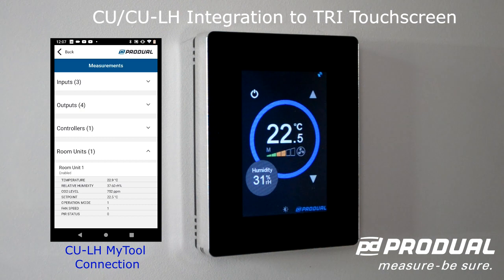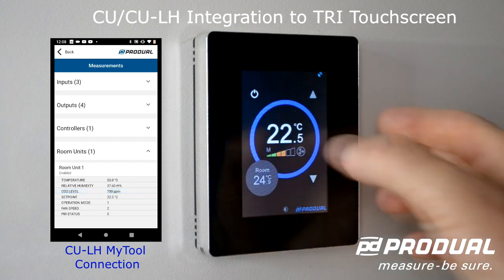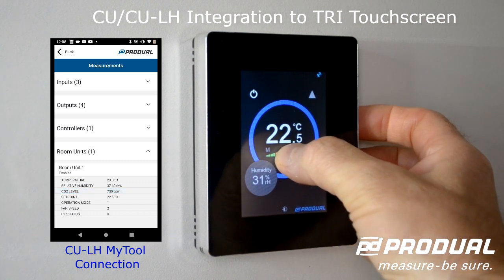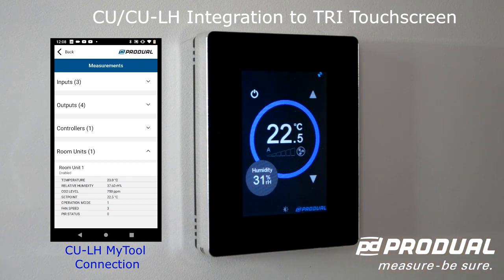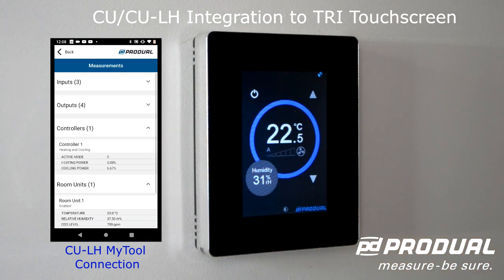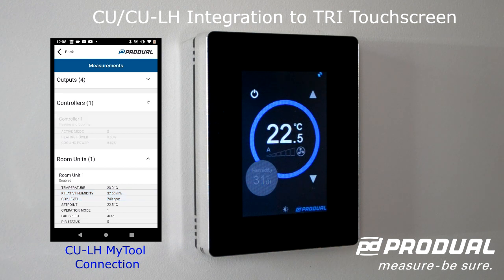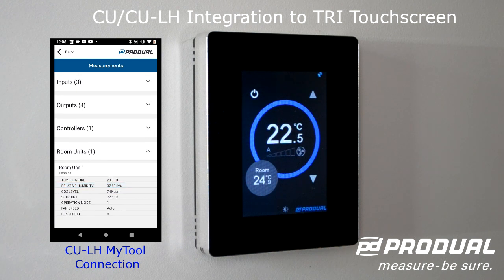speed 2. This signal is now sent to the CU/CULH using a Modbus input register 2, and now the controller will start to control to a manual fan speed 2. If we go to fan speed 3 and then we go to automatic, now the TRI sends the message to the CU and CULH saying the device is in automatic mode. So the user is asking for automatic control, and now the CU and CULH will start control to the automatic settings and configuration inside the device.